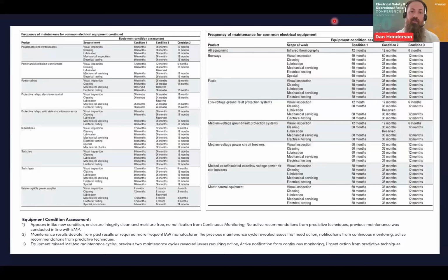So we're going to focus on NFPA 70B because it's quite prescriptive, which is good, gives some good direction. We're just going to use that as an example and then try and look between the gaps of the prescribed maintenance frequencies. So again, if you're not familiar, there's some tables in there. It gives you details on the maintenance within there as well, but the tables as a reference. So you've got the product, so panel boards, power cables, and then it's got some key tasks in there like cleaning, inspection, mechanical, electrical testing. You'll notice on all equipment, it's got infrared thermography every 12 months.